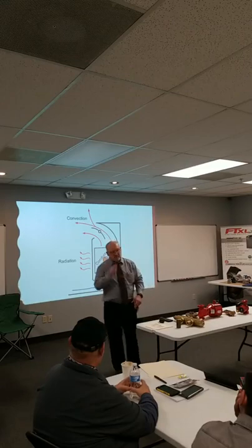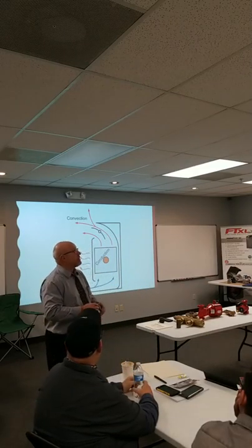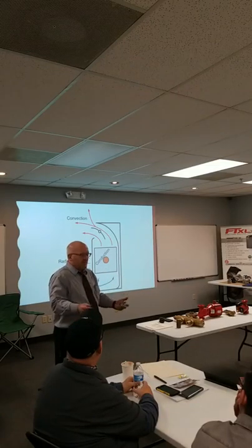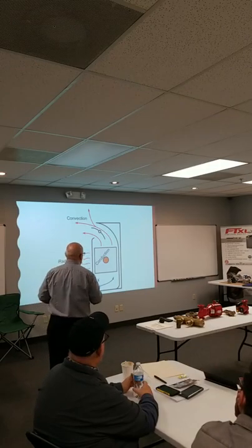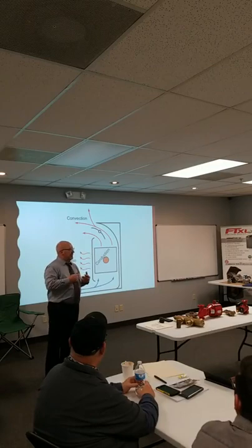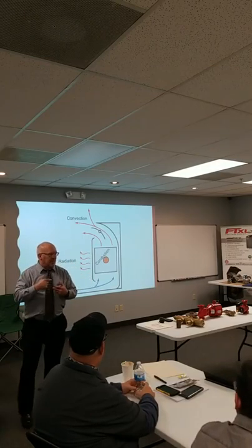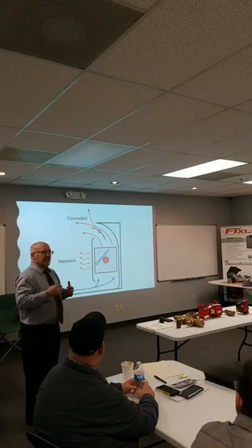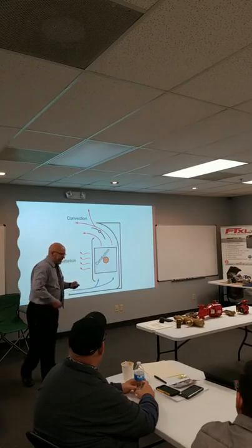And I said, let's try something. I picked up the corner of the rug, and you could just feel the heat coming off of this thing. You're covering up your radiator. You're hiding the heat from going out. You're insulating it. So being able to get heat out is very important, because if we don't get the heat out, it's going back to the boiler, and the boiler's going to go out on limit, even though there's calls for heat, because it's not dissipating the heat. So we have to get rid of those BTUs, and that's what we're trying to do.